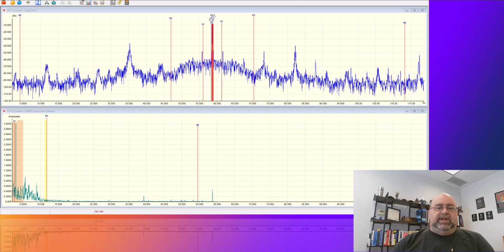So this would be 27.93 plus this. Just for the sake of it, we'll start out with 27 plus 60, which would be 87, 88 roughly, minus about 1.5, so about 86.5. So we are going to be right about here. This may be it, a small peak right around 85. And then we're going to go to the opposite side and look for the same thing. That's going to be roughly about here. So not significant. Next one is going to be 21.32 hertz. That would be 81, or basically 79. So somewhere in here, maybe this peak, and then also right about here. I'm not seeing solid peaks coming up that would be high enough to show an issue with these.